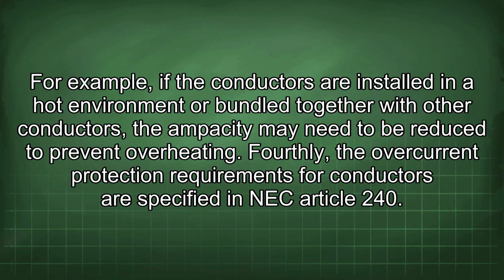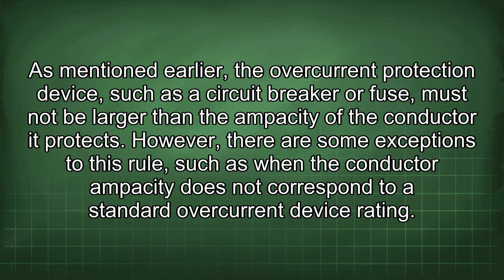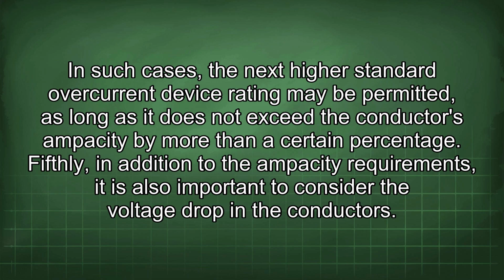Fourthly, the overcurrent protection requirements for conductors are specified in NEC Article 240. As mentioned earlier, the overcurrent protection device, such as a circuit breaker or fuse, must not be larger than the ampacity of the conductor it protects. However, there are some exceptions to this rule, such as when the conductor ampacity does not correspond to a standard overcurrent device rating. In such cases, the next higher standard overcurrent device rating may be permitted, as long as it does not exceed the conductor's ampacity by more than a certain percentage.